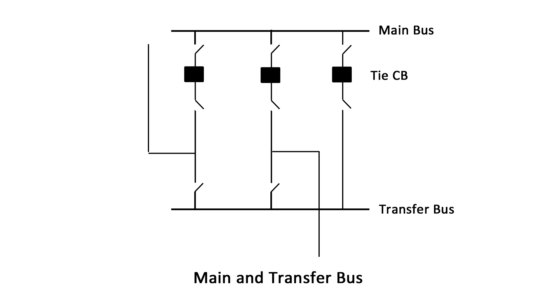One or more circuit breakers may be used in this arrangement to make connections between the main and transfer bus. When no tie circuit breaker is present, for maintenance of a circuit breaker, the transfer bus is energized by closing the isolator switches to the transfer bus.